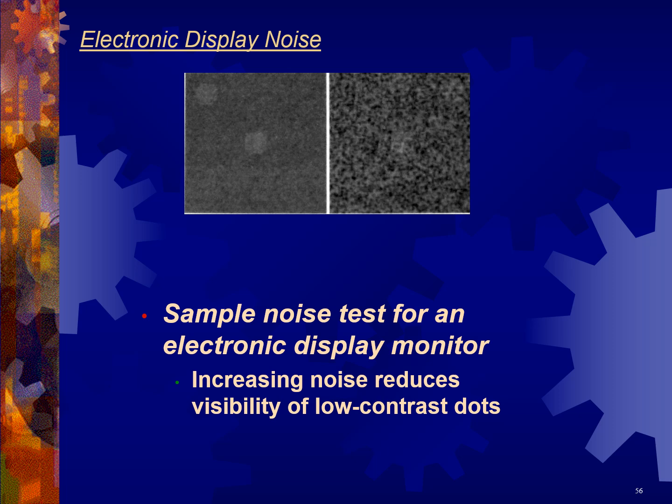Okay, so increasing noise reduces our ability to spot low contrast differences, and so this is the standardized test. This just noticeable difference test tests for the noise level of your monitor, but ultimately it's subjective, and it's up to your radiologist how much noise is tolerated and not tolerated.